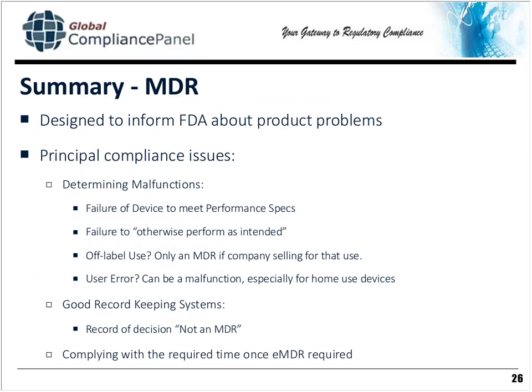Okay, so here's our summary on MDRs. We still have to talk about removals and corrections, and if there's time, perhaps the electronic problems. But anyway, the MDR is designed to inform FDA about product problems that will pose a health problem. The principal compliance issue from a review of MDRs has been determining malfunctions, that is, the failure of the device to meet its performance specs or failure to perform otherwise as intended. That's a direct quote from the regs.